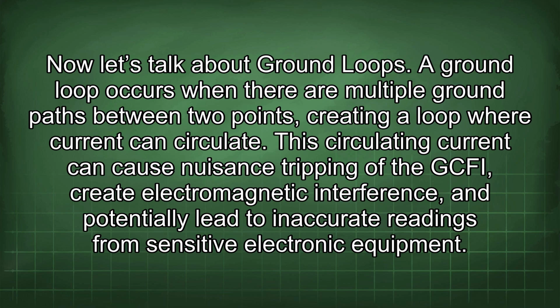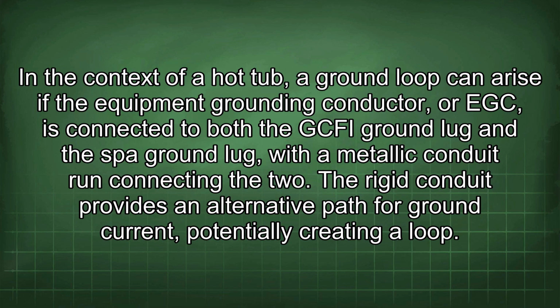Now let's talk about ground loops. A ground loop occurs when there are multiple ground paths between 2 points, creating a loop where current can circulate. This circulating current can cause nuisance tripping of the GFCI, create electromagnetic interference, and potentially lead to inaccurate readings from sensitive electronic equipment. In the context of a hot tub, a ground loop can arise if the equipment grounding conductor, or EGC, is connected to both the GFCI ground lug and the spa ground lug, with a metallic conduit run connecting the two. The rigid conduit provides an alternative path for ground current, potentially creating a loop.